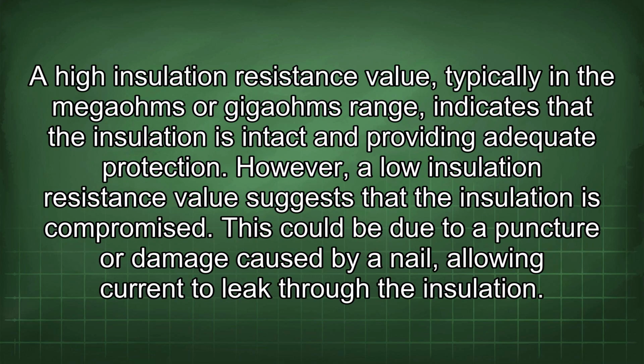A high insulation resistance value, typically in the megohms or gigohms range, indicates that the insulation is intact and providing adequate protection. However, a low insulation resistance value suggests that the insulation is compromised. This could be due to a puncture or damage caused by a nail, allowing current to leak through the insulation.